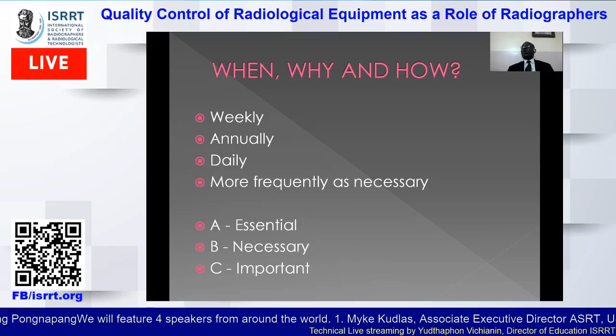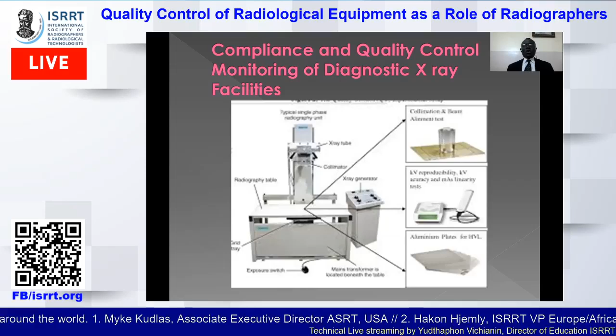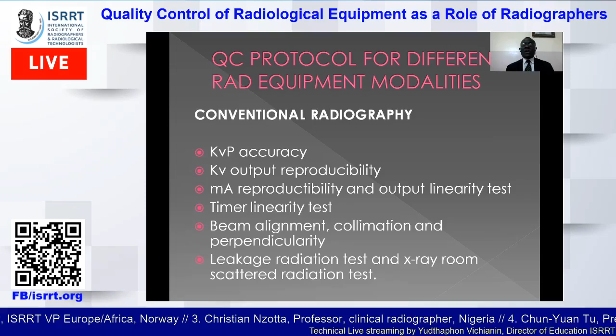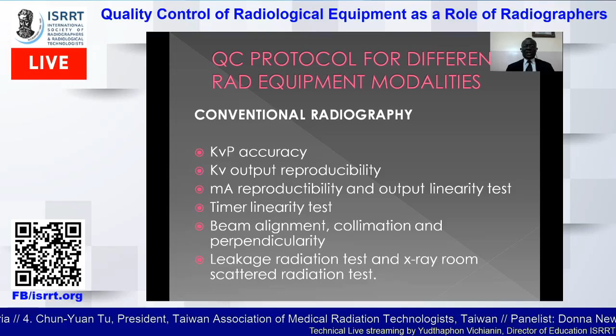As you can see, these are the various equipment that should go through quality control procedures and the meters used. Some of these equipments are not very well known to the radiographer or the quality control team. It is also important for us to note that there are different protocols for quality control depending on the type of modality. For conventional radiography, the major criteria for quality control include the measurement of the kV accuracy, the kV output reproducibility, the mA reproducibility, the output linearity test, the timer linearity test, the beam alignment, collimation, and perpendicularity. Leakage radiation tests and X-ray room scatter radiation are tested on a regular basis.